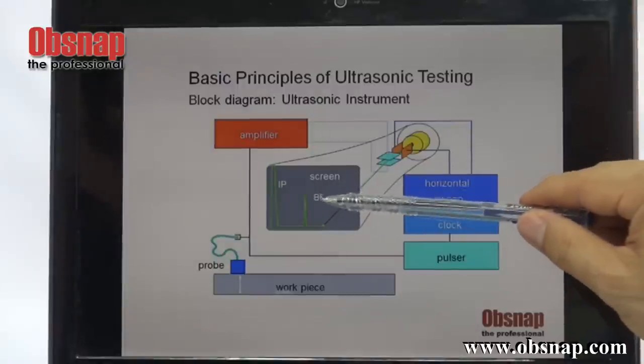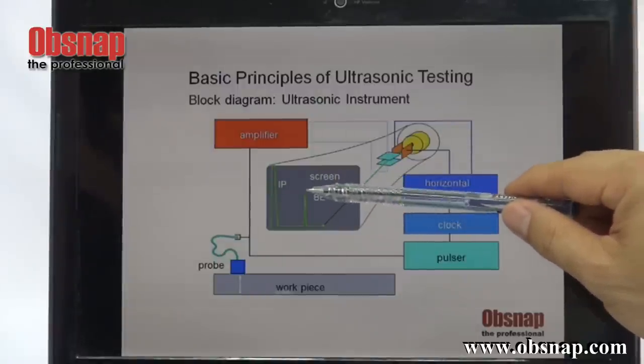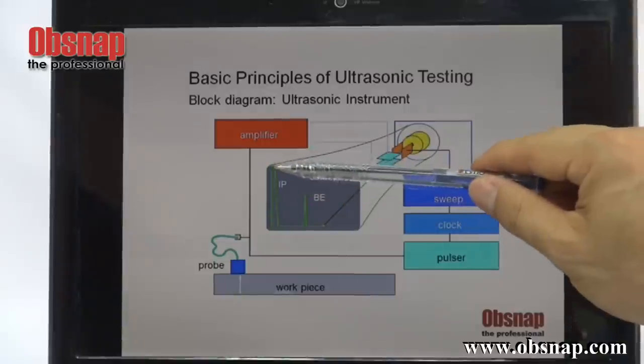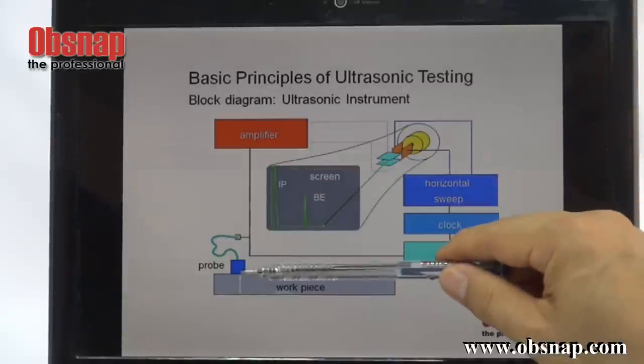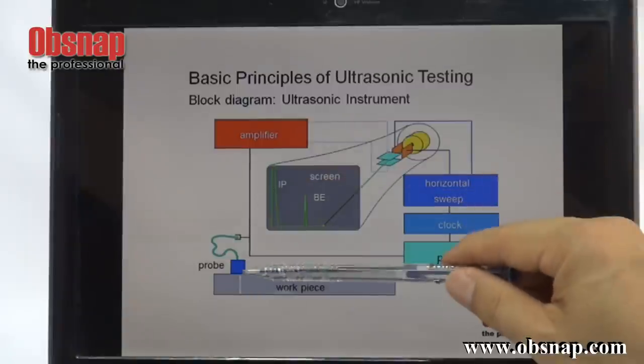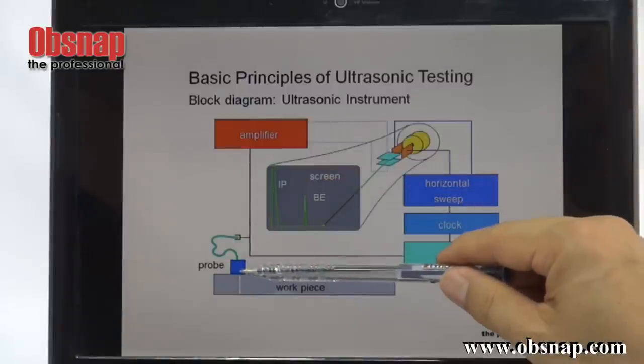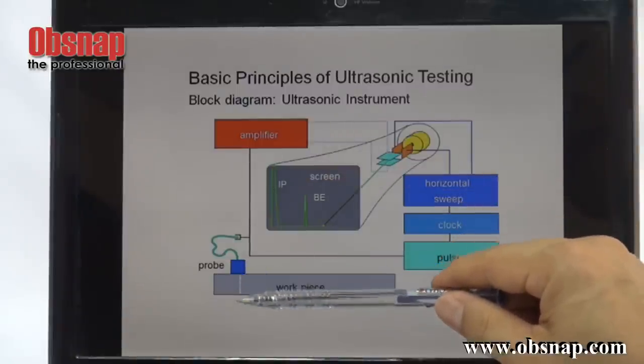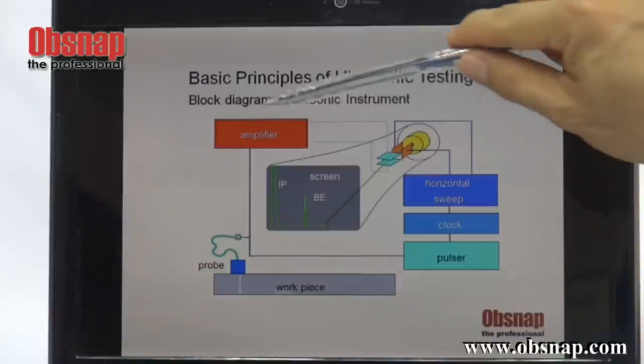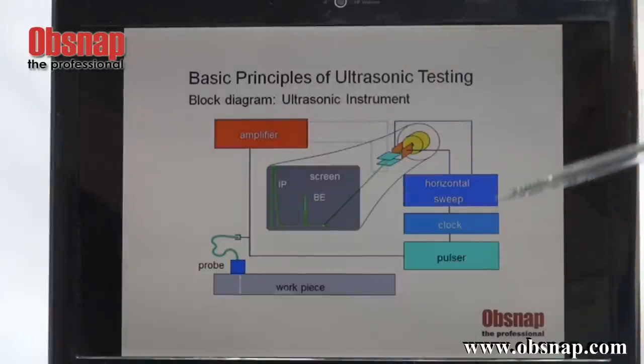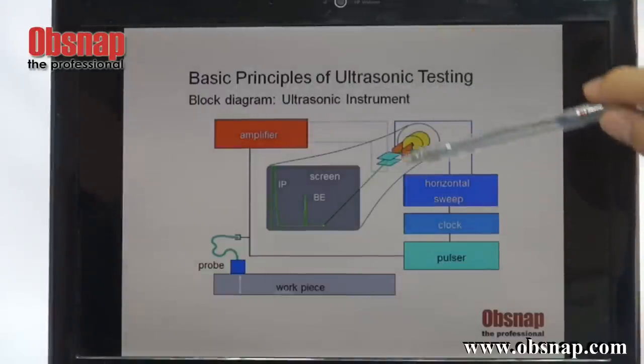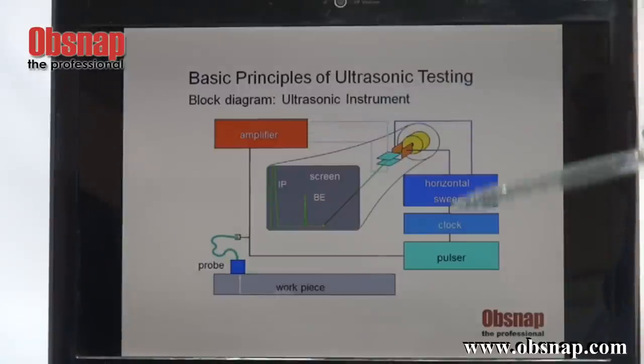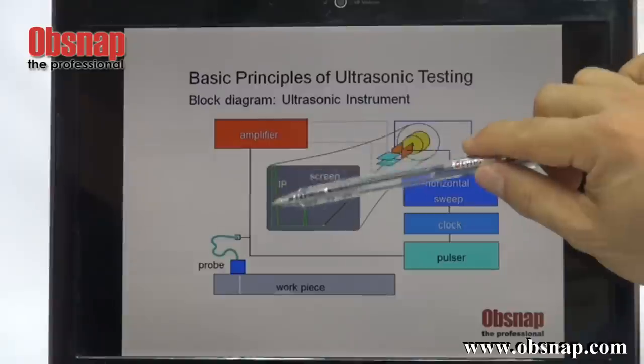How this pulse is generated is when the sound wave travels into the material and is then reflected by the back wall — B.E. stands for back wall echo. The amplitude of the back wall echo is usually lesser than the initial pulse amplitude, because there are some losses of energy or strength when it actually travels in the material. The rest of the functions in the main unit are to display the pulse.